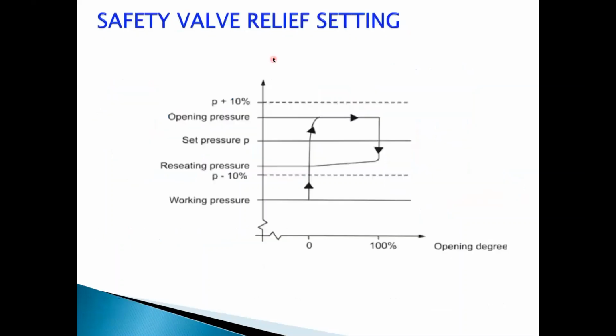Typically, a good safety valve will operate at a set pressure with less than 10% margin. It means you are set at, say, 300 psi. It should open fully before 330 psi and should close before 270 psi. The main advantage of this operation is that it saves a lot on refrigerant release. It protects the environment, protects against the effects of refrigerant leakage, and also keeps the system stable.